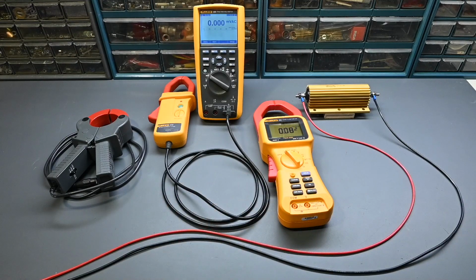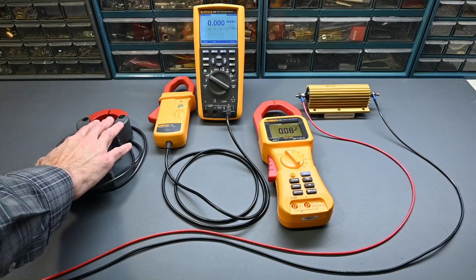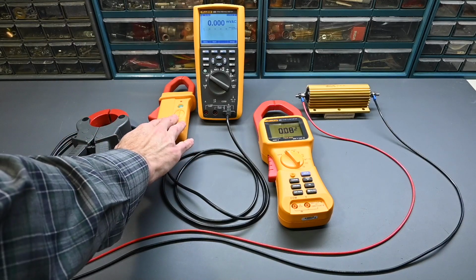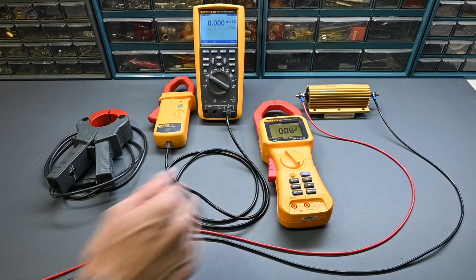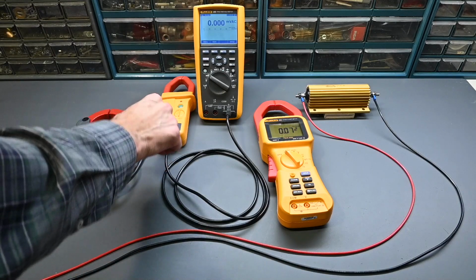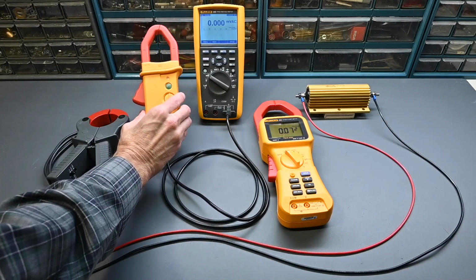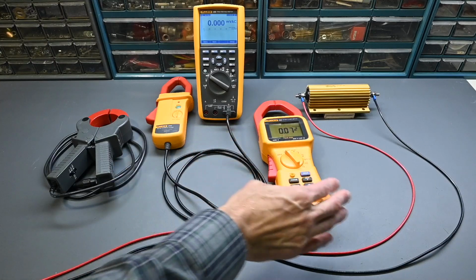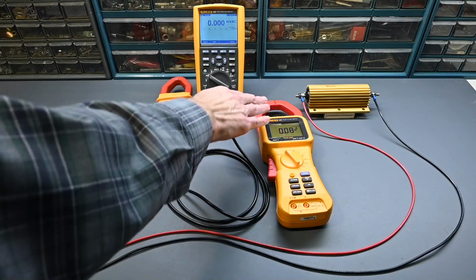Now some types of current clamps are AC current only, and they essentially work by using the current transformer principle, but other types are AC and DC current, and they use a Hall effect sensor to detect the current flow. So this current clamp right here is AC current only, this is AC and DC, and this current clamp is AC and DC. Now the Hall effect sensor requires power, usually batteries inside the current clamp. So there's batteries inside this current clamp, and you can see the power on indicator light right there. And of course this clamp has batteries in it as well. There's a number of other features in this clamp and a display, but of course that Hall effect sensor requires power.